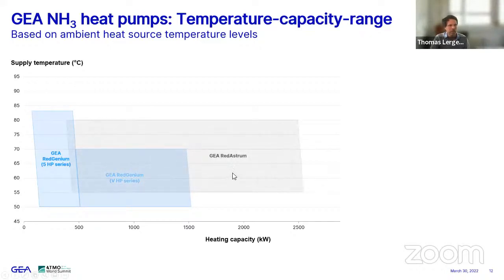We have a screw compressor heat pump that's called GEA RedGenium. It provides larger capacity range and temperatures up to 80 degrees Celsius. If we are leaving the standard range and go a little bit more into our customized equipment, then we can provide higher temperatures up to 85 and very large capacities up to 10 megawatt per unit. The capacities are very much depending on the temperatures.